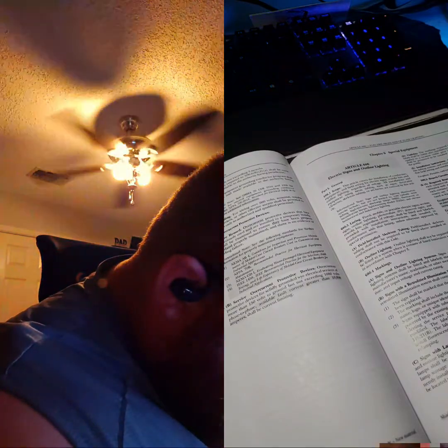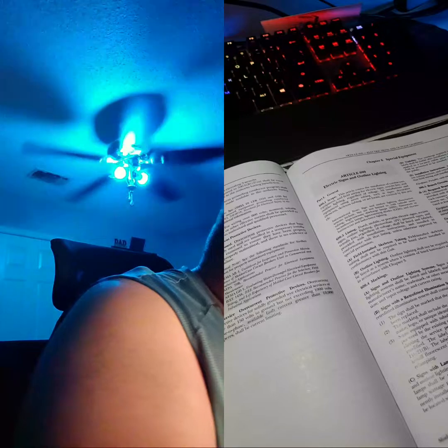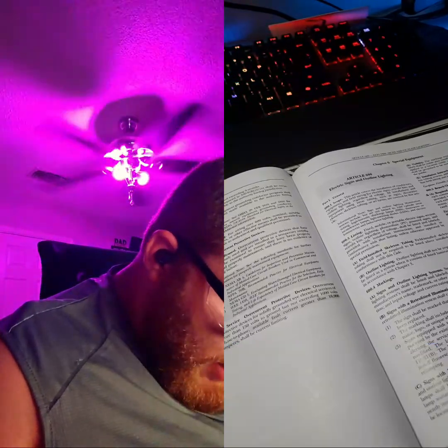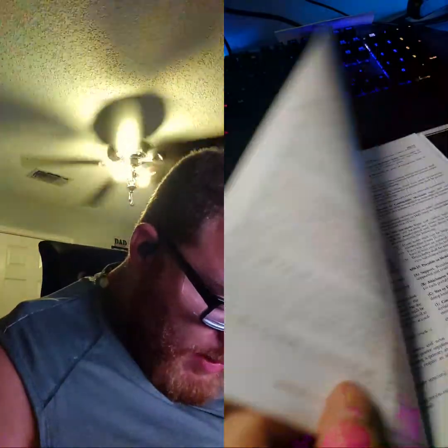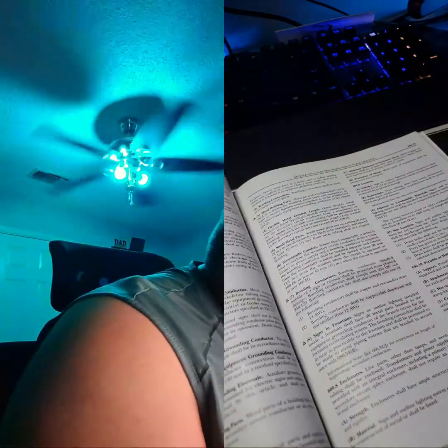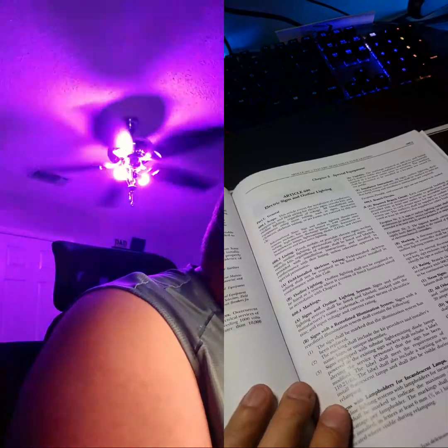Rating. Branch circuits that supply signs shall be rated in accordance with 600.5(B)(1) or (B)(2) and shall be considered to be continuous loads for the purpose of calculations. Neon signs: branch circuits that supply neon tubing shall not be rated to exceed 30 amps. All other signs: branch circuits that supply all other signs and outline lighting systems shall be rated not to exceed 20 amps. So it's probably 20 amps. Easy peasy.